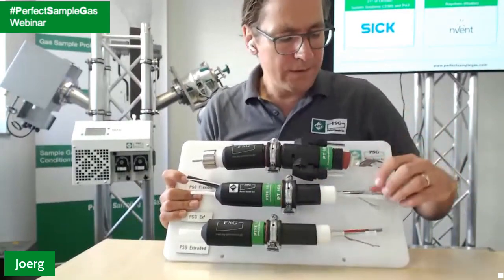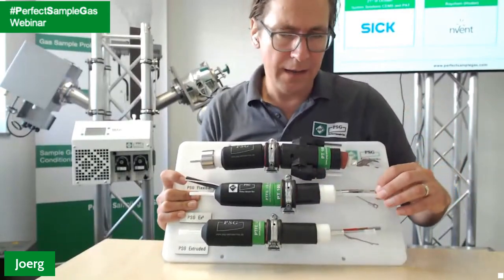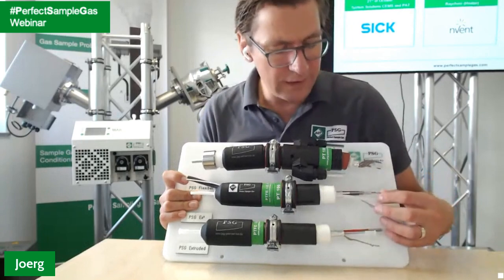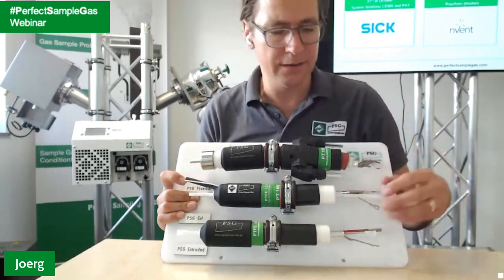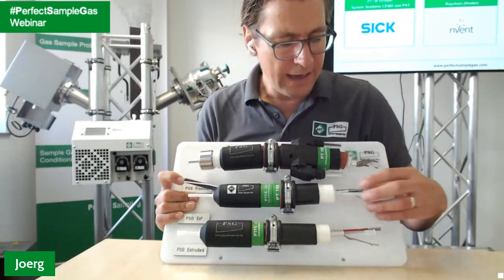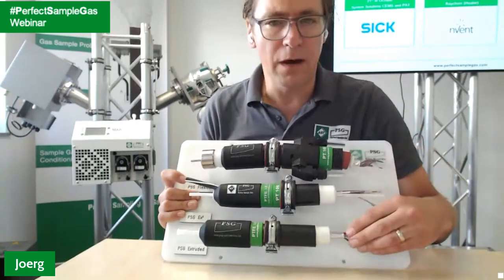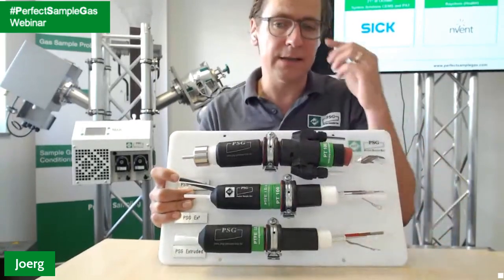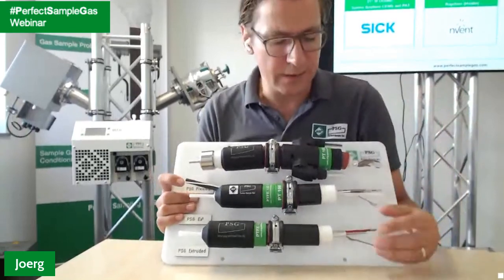So this type of line, we have highly developed technology. Here, first of all, we have two different types of heaters: parallel heaters, where the heater is parallel to the probe tube, and at the same time they have a lot of power output. Not as much as 90 watts per meter, but 60 watts per meter.